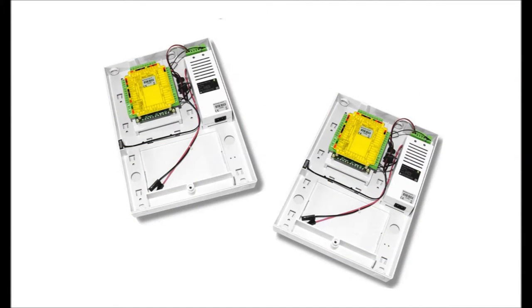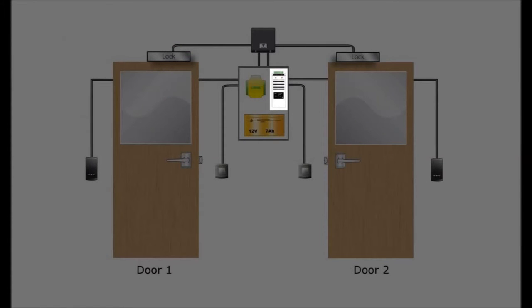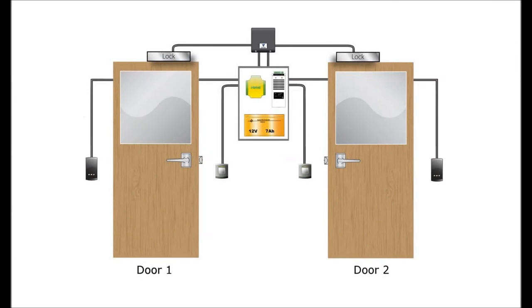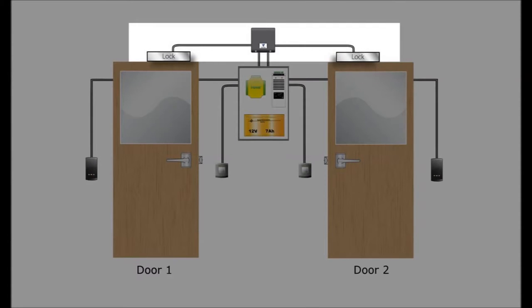The Net 2 ACU power can be used provided it has sufficient capacity for the interlock and lock as well as the ACU and its readers. Net 2 will determine the access when a token is presented, but the interlock will only open the relay provided the two doors are in the correct state.